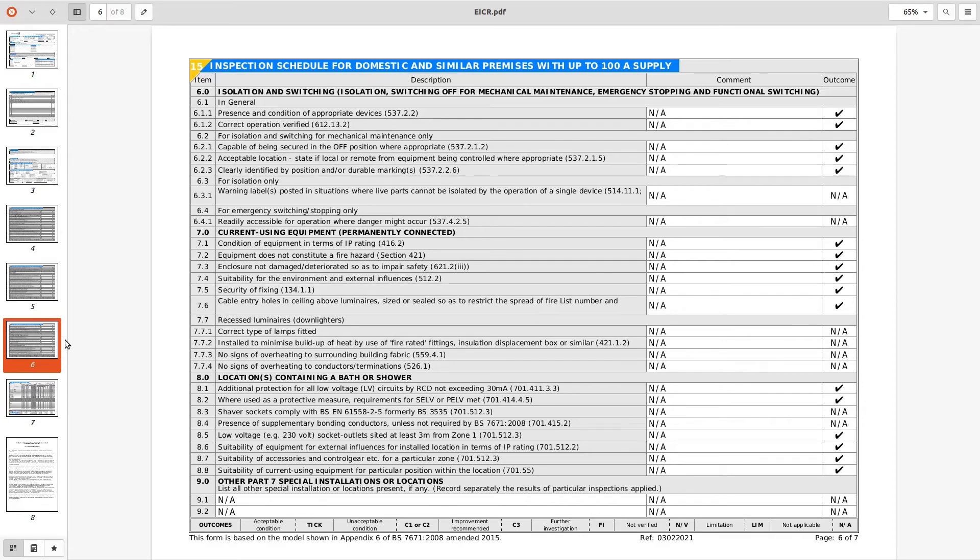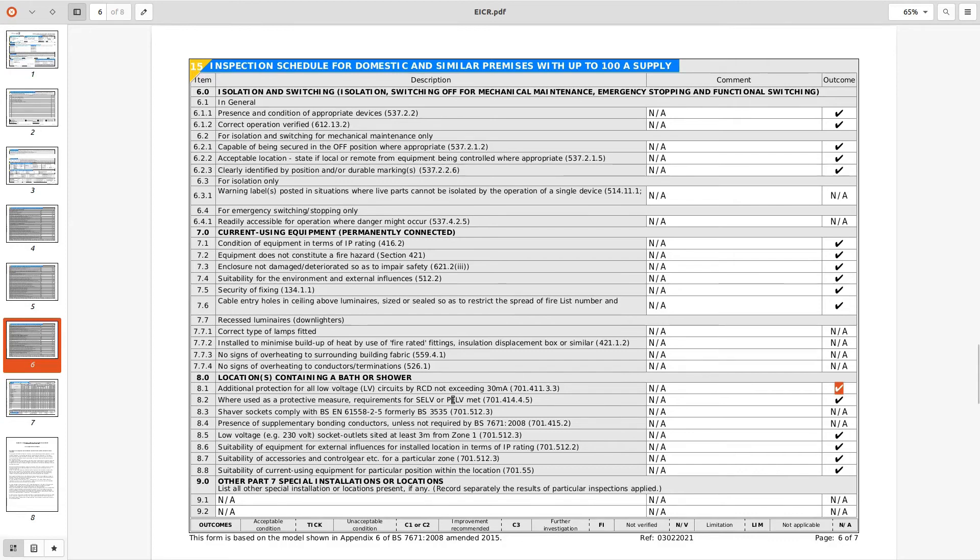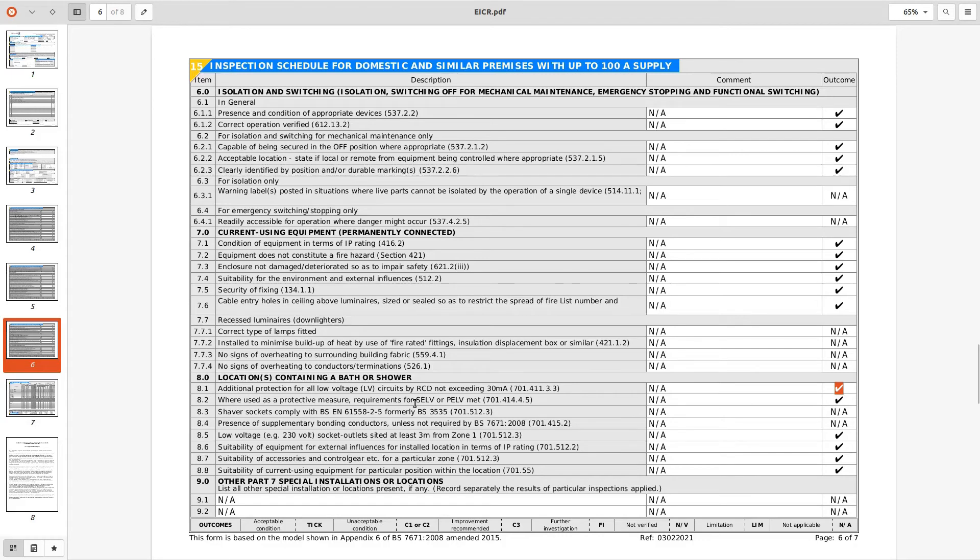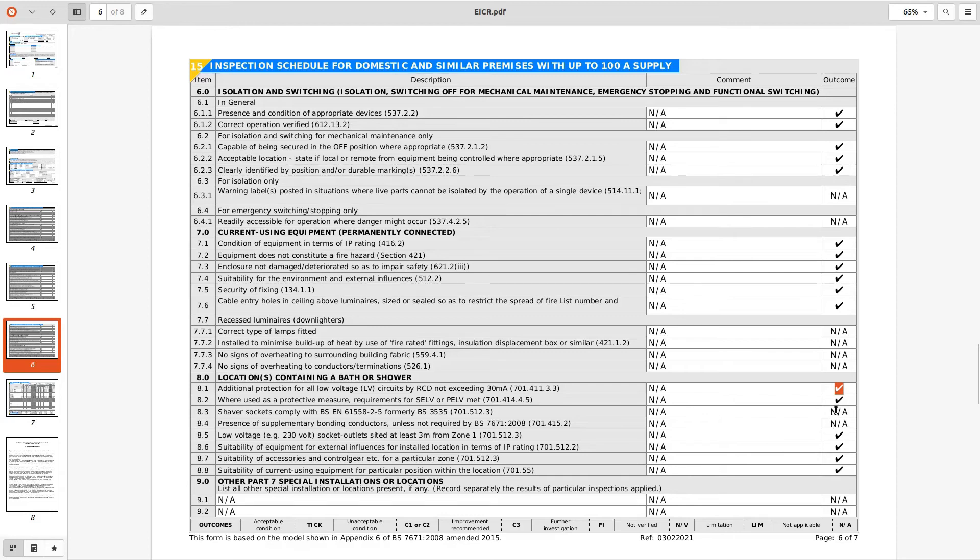Next page, third page that looks pretty good I think. Look at this, locations containing a bath or shower additional protection by RCD, he's put a tick in there, so we have got RCD protection for the bathroom is what he's saying. But I would think circuits one to six would include the bathroom. Protective measure against, do we have down lights there maybe, do we have down lights in the bathroom with RCD protection? Now if this is a 25 year old property likely to have the MR16 type lamps, SELV transformer, so they could have down lights which means then he would have been taking some of these things here. But I'm not quite sure at this point I'm getting a little confused, RCD, no RCD, down lights perhaps, no down lights, I'm not sure.